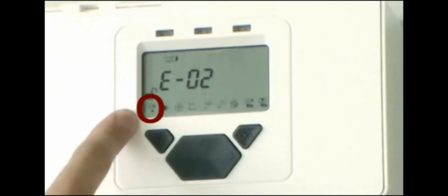The next step is to find how many receivers are connected to the system controller. Access Find by highlighting the first icon on the left and pressing the checkmark button. To start the automatic find sequence, press the checkmark button a second time. The display shows a countdown while finding receivers. If one receiver is connected, the countdown will take 10 seconds. If 2 receivers are connected, the countdown will exit as soon as both receivers are found. The receiver icon at the top left of the display shows which receivers have been found. The display also shows 2R to indicate the number of receivers found.